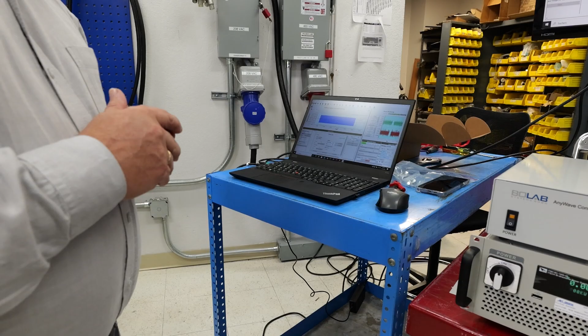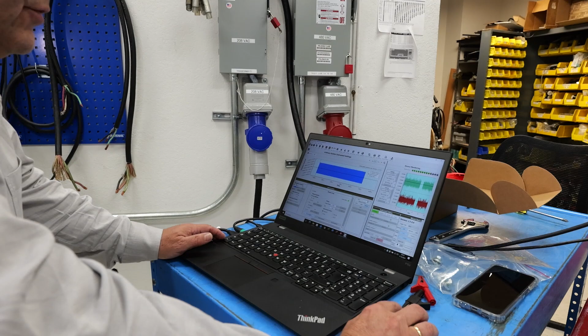As the first thing, we have a software with closed loop functionality, and with this closed loop functionality we run a calibration routine. We say start, and now the calibration routine is running. It is generating a small voltage ripple from DC to 250 kilohertz, and while this frequency is running, the voltage is measured. In the next run we generate a small voltage ripple again, but this time we capture the current. Out of these frequency values, we calculate the impedance.